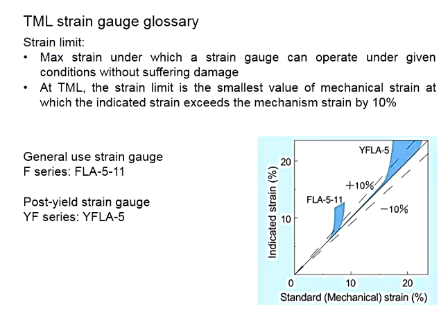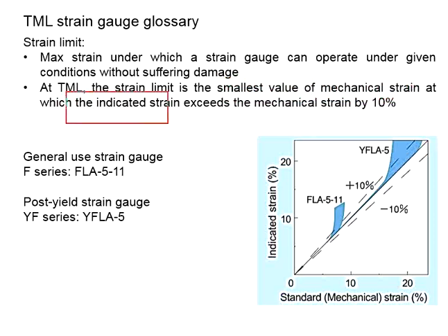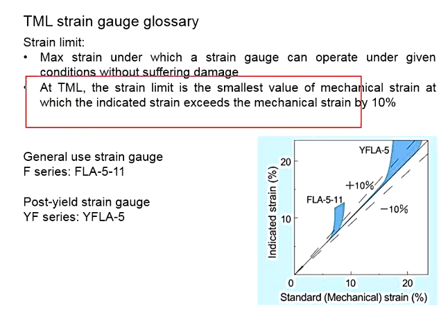Next, we talk about the strain limit. This refers to the maximum strain under which a strain gauge can operate under given conditions without suffering damage. Every strain gauge has its own limit. Beyond this limit, the strain gauge will be damaged and the result cannot represent the actual situation of the member. Based on the definitions of TML, the strain limit is defined as the smallest value of mechanical strain at which the indicated strain exceeds the mechanical strain by 10%.